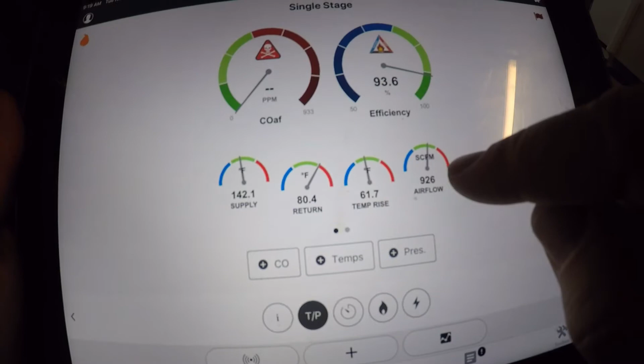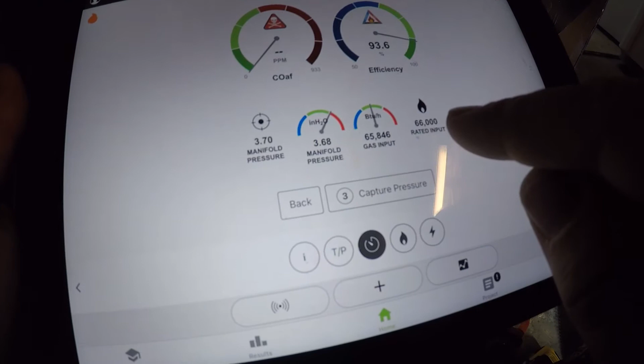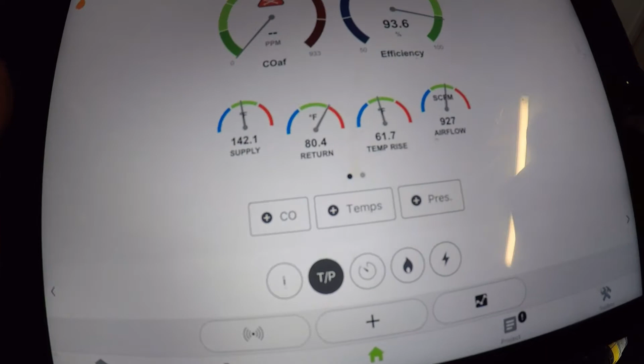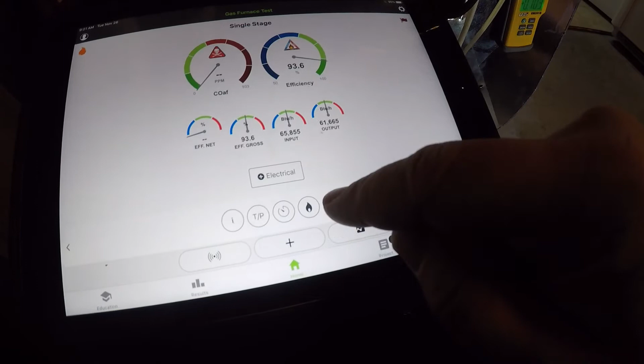At the same time, it will give me my airflow, which is pretty much bang on with what the ECM readout is. And the way we get that is once we've got our input correct and all our other metrics, it's able to calculate a value for estimated airflow. And lastly, I'll take my electrical readings with the Redfish meter, and I'll show you how that's done. So I'll go to my toolbox and connect my meter.